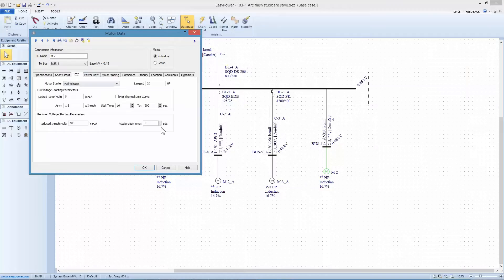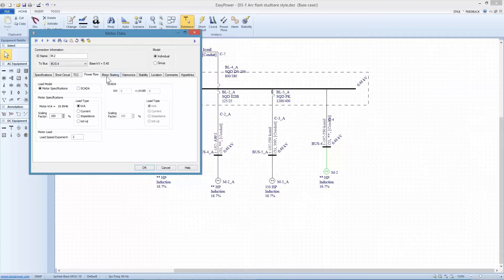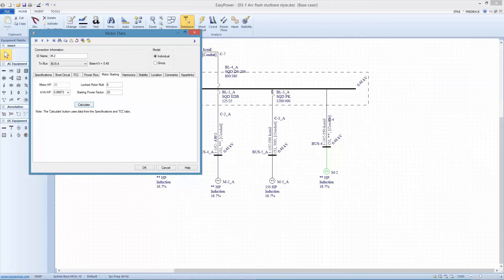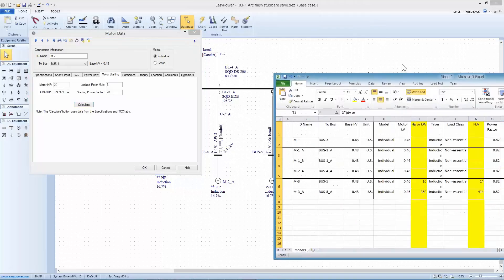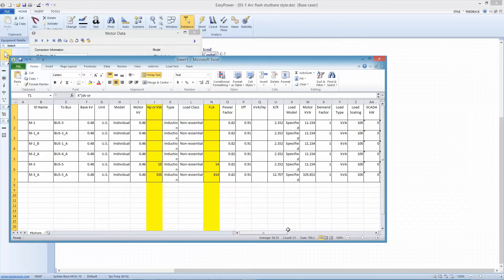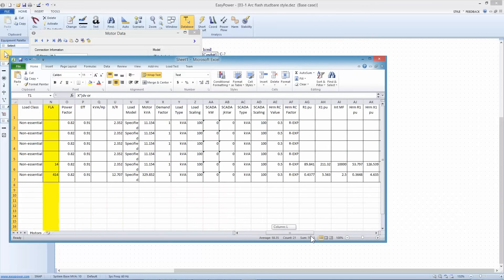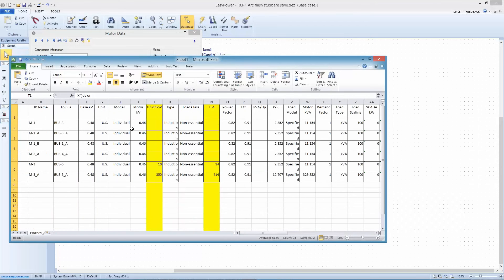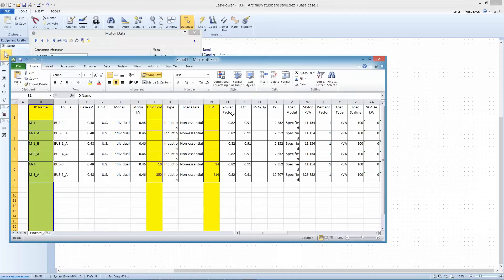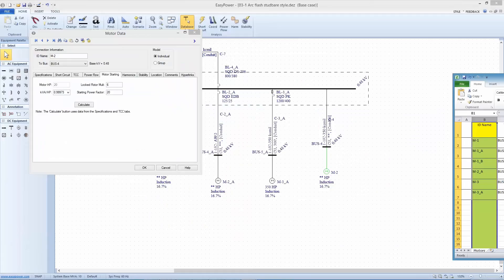TCC, there's nothing to enter. Power flow, there's nothing to enter. Motor starting, if I do calculate, it comes up with all the parameters based upon data that's already entered. So for the most part, motors are relatively straightforward as long as I don't have any anomalies. This really boils down to primarily the horsepower, the name, the ID name, and then anything that's non-standard in terms of the power factor, efficiency, or full load current. Most of the rest of this chart is not necessary.